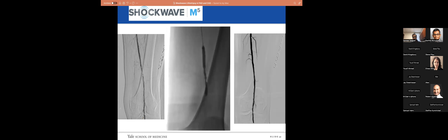And this is what the balloon looks like when it's inflated to 4 atmospheres in the peripheral, which is a huge waist on the balloon, where there's angiographic calcium on both sides, double walls of the vessel. And that was the final result after the angioplasty with Shockwave alone and no other adjunctive treatment. This is the S4 catheter, which is recommended for below the knee use, but you can really use it in any situation that you feel it's necessary in the peripheral space.